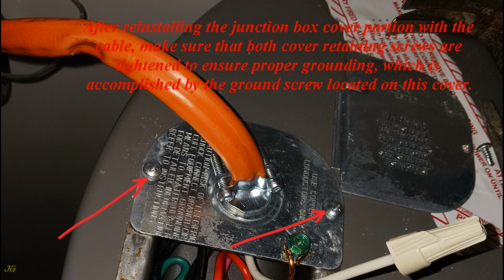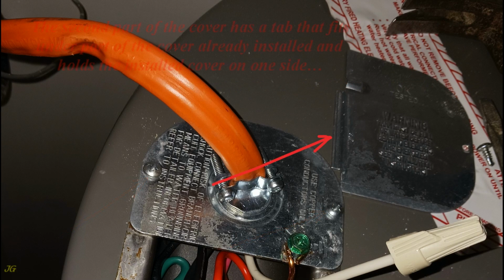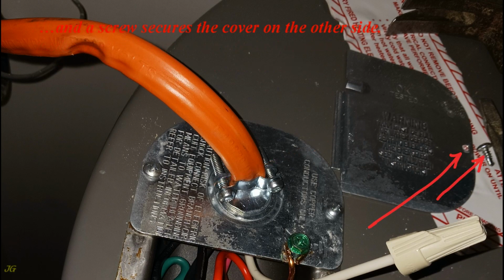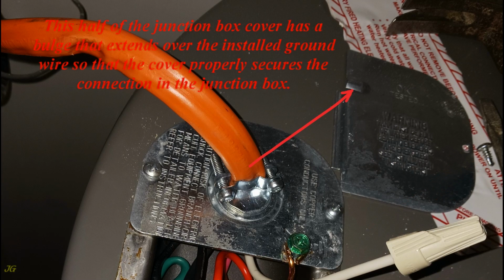After reinstalling the junction box cover portion with the cable, make sure that both cover retaining screws are tightened to ensure proper grounding, which is accomplished by the ground screw located on this cover. The second part of the cover has a tab that fits under part of the cover already installed and holds the installed cover on one side, and a screw secures the cover on the other side. This half of the junction box cover has a bulge that extends over the installed ground wire so that the cover properly secures the connection in the junction box.